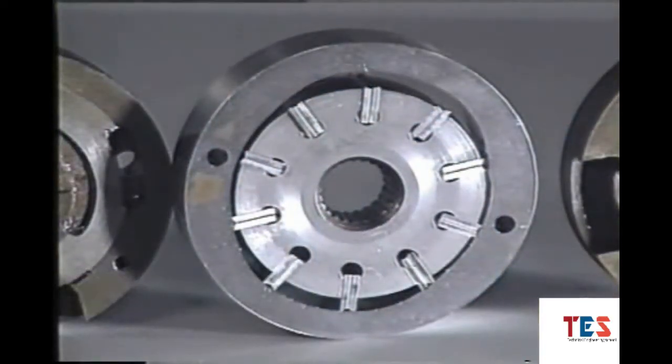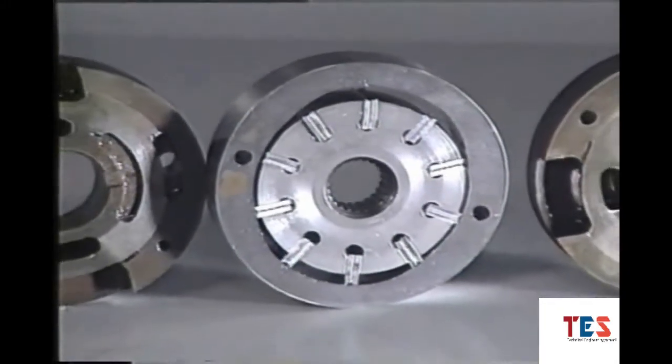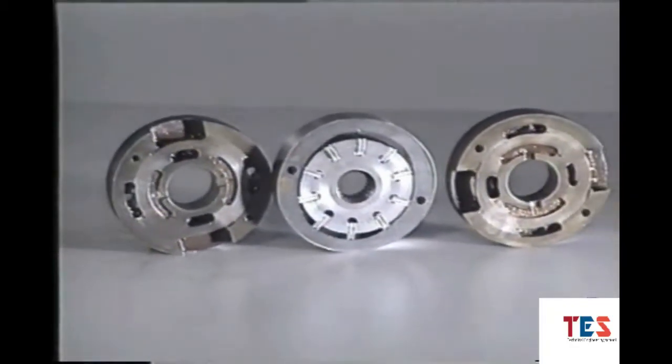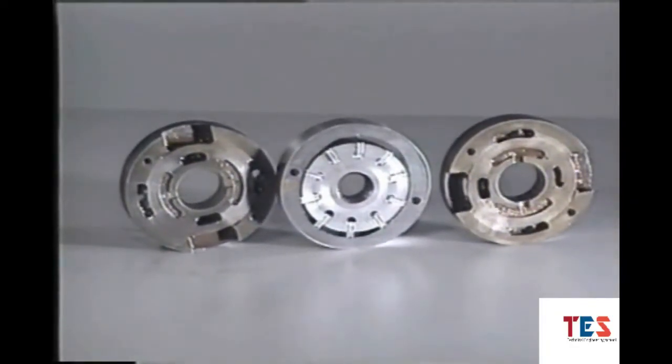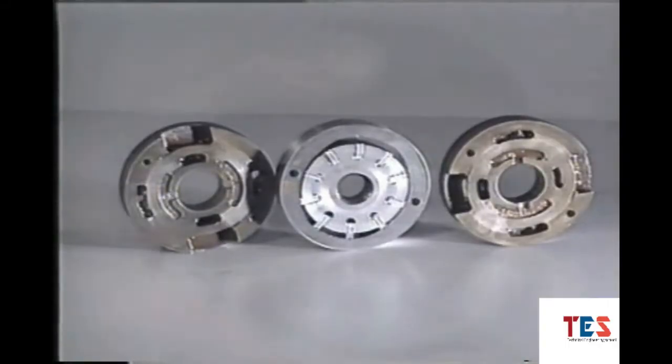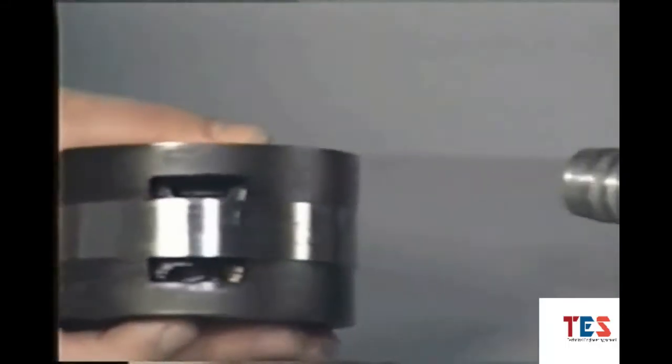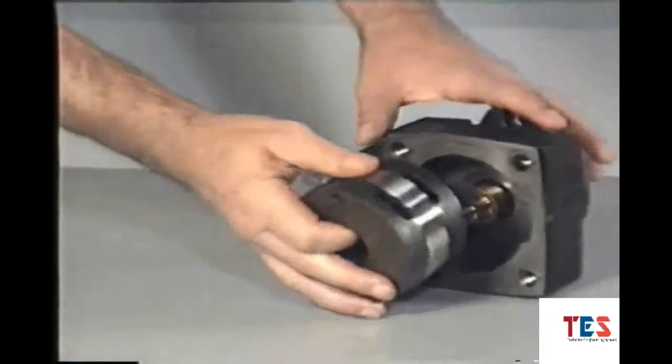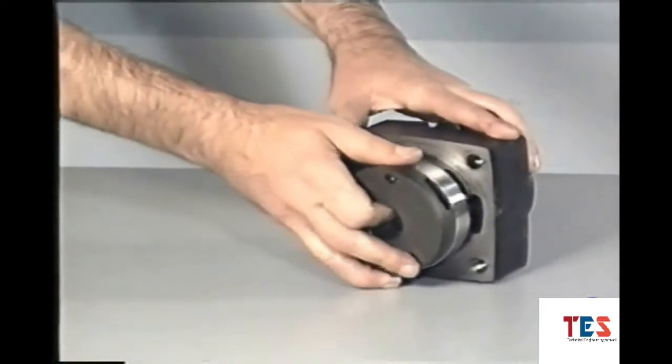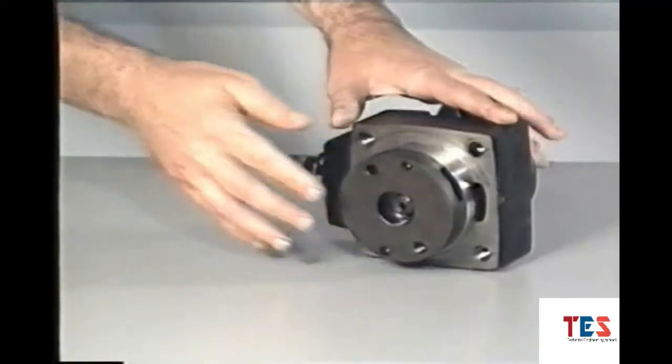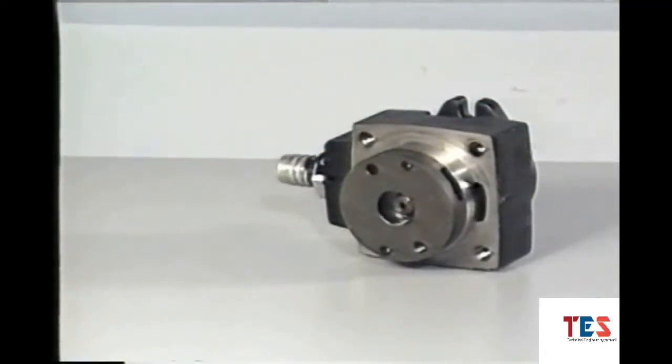Let's examine the vane pump first. The vanes fit into the rotor and slide in and out as the rotor turns inside the ring. The ring with its rotor and vanes is sandwiched between the port plates which have holes or ports. Fluid moves through these holes into the pump and back out again. The entire package is called a cartridge assembly and it's encased in the pump housing.